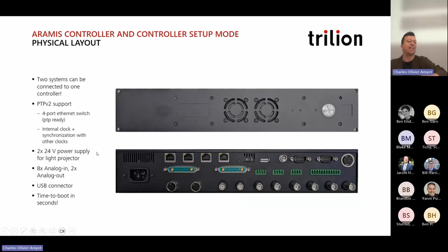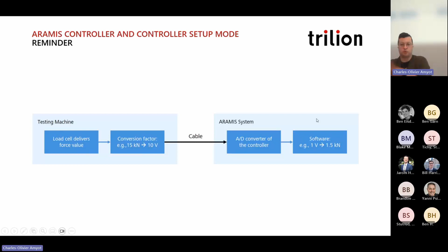Currently, if you have a load cell with a load value as a 0 to 10 volt signal, you need to set up a conversion factor, then read it into the system with the ARAMIS controller and transfer that into a force signal. We've added new controller setup modes into the setup workspace, allowing you to configure and define the analog inputs and outputs, as well as your triggers and filters.